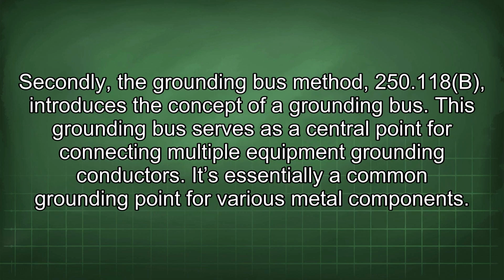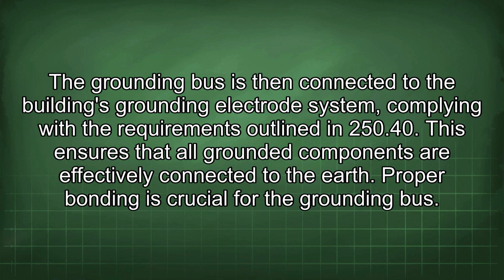Secondly, the grounding bus method. 250.118 B introduces the concept of a grounding bus. This grounding bus serves as a central point for connecting multiple equipment grounding conductors. It's essentially a common grounding point for various metal components. The grounding bus is then connected to the building's grounding electrode system, complying with the requirements outlined in 250.40. This ensures that all grounded components are effectively connected to the earth.